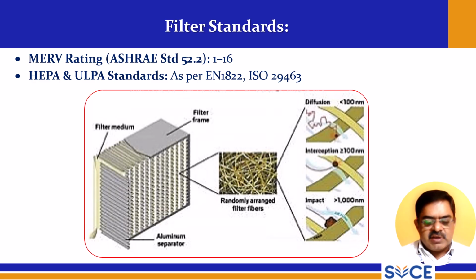So this is the HEPA filter. This is the filter medium, the filter frame, and these are the filter fibers, randomly arranged. Diffusion is for particles lesser than 100 nanometers, and interception and impaction are in terms of nanometers. An aluminum separator is provided here. This is the simple construction of a HEPA filter.